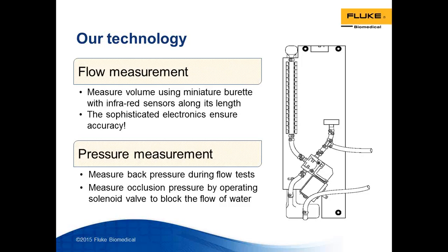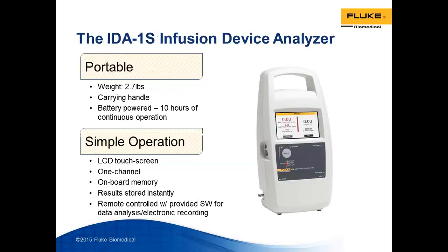I won't get into that too much, but talking specifically about the products themselves, the technology I just mentioned consists of a flow measurement technique which involves a miniature burette with infrared sensors along its length. So it's pretty sophisticated technology for calculating flow. On the occlusion end, both devices, the IDA-1S and IDA-5, measure back pressure during flow tests, but the occlusion pressure is essentially calculated by operating a solenoid valve to block the flow of water and creating an occlusion scenario. So those are the 2 important baselines for both of our products.